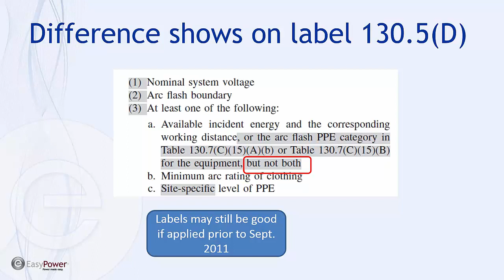Now, that's one way to work with this. It's not the only way to deal with it, but it does emphasize, I guess, my underlying point, and that is the migration that I see in NFPA 70E is to emphasize more and more things like maintenance and worker training, and somewhat at least put them on the same footing as we've been talking about incident energy calculations. It's good and it's important to understand the energy that's contained in the bus, but it's equally good and important to understand that the maintenance of the facility and the piece of equipment are equally as important and have as much to do with the potential for a catastrophic event as putting on a set of gear or set of specific clothing.